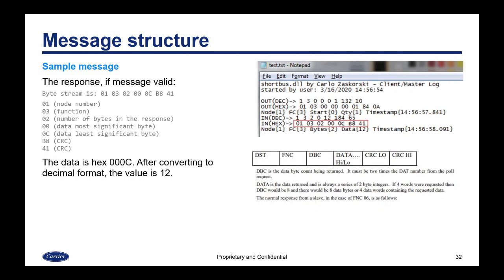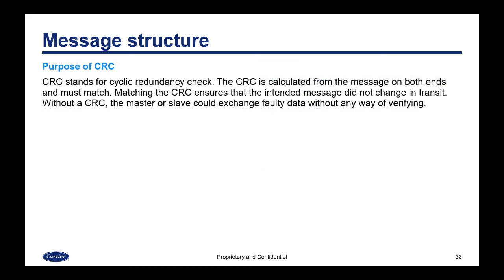The response, if the message is valid, will include much of the same identifying information, but will also include the result — the data will be presented in bytes in the return message. The purpose of the CRC (cyclic redundancy check) is to verify that the message is valid on both ends. The CRC is calculated from the message and must match. Matching the CRC ensures that the intended message did not change in transit. Without a CRC, the master or slave could exchange faulty data without any way of verifying it.